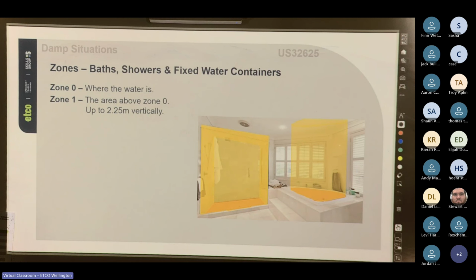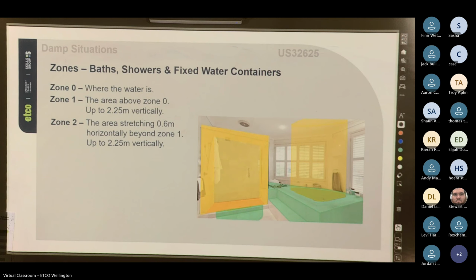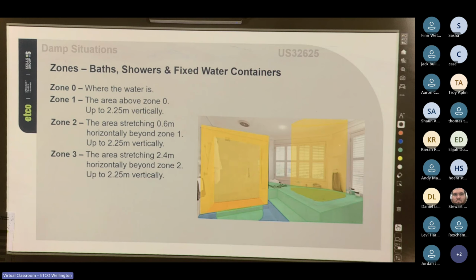But then as we move from zone 1 to zone 2, the area stretching 0.6 meters horizontally beyond zone 1 up to 2.25 meters. So it's basically 0.6 meters away or 600 mil away from the rim of the bath or the entry into the shower. And again, still up to 2.25 meters vertically. So that height doesn't change. And then we have zone 3, the area stretching 2.4 meters horizontally beyond zone 2 up to a height of 2.25 meters vertically. So the zones reach up to 3 meters away from the edge of the water container.